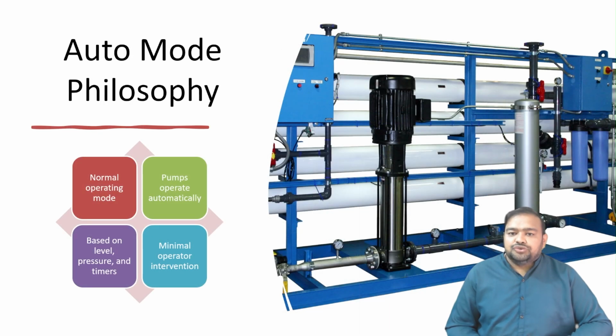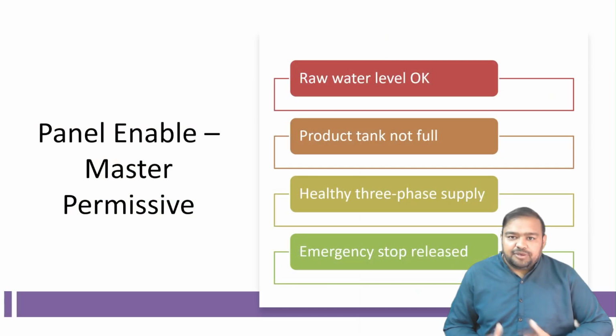Auto mode is used during normal plant operation. In auto mode, the pump starts and stops automatically. Operation is based on level, pressure, and timers. Operator intervention is minimal, and auto mode is where the real control logic exists. Before any pump can start, the panel itself must be enabled. Panel enable depends on the following conditions: raw water tank level above low, product water tank below high level, healthy three-phase supply, and emergency stop released. If any of these conditions fail, the panel disables all pump operation.